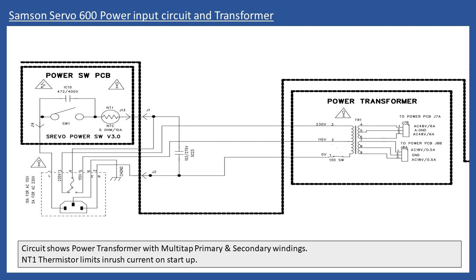And if you look on here, this is very common, the manufacturer will normally tell you the protection fuse rating required on the power input depending on the supply voltage. So here they're showing you that if you're running the amplifier on 230 volts, you need a 5 amp protection fuse, but if you're running it on 115 volts, then it's going to be 10 amp. So you can see as the voltage got halved, the current doubled, so the protection fuse needs to be increased. And normally this is a time delay fuse, a T-type thermal delay fuse, not a fast blow, because of this inrush current that you see.